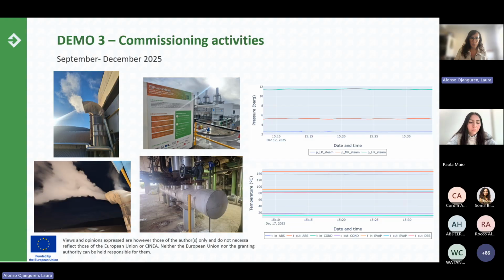And here we can see some graphs showing the different conditions we got in those trials. So we can see the three different pressures in the thermocompressor. The low pressure steam coming from the flash tank at around 2.3 bar G. The high pressure steam coming from the plant, and the medium pressure steam at around 5.5 bar G, which is the useful steam injected into this medium pressure steam header.